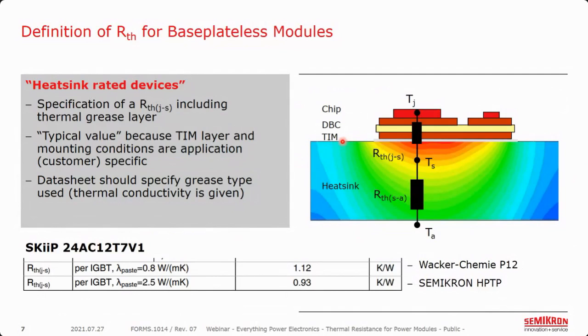Power module manufacturers use the linear thermal model where we make a thermal circuit representing the power loss as a current source and the voltage drops — in quotes — across these thermal resistances as temperature changes or deltas. Looking at the simpler base plate-less module, we can see two thermal resistances: R-theta junction-to-sink, which includes the effect of the thermal grease or thermal interface material (TIM), and R-theta sink-to-ambient, the thermal resistance between heat sink and coolant. Since we don't have a case, base plate-less modules are sometimes called heat sink-rated devices.